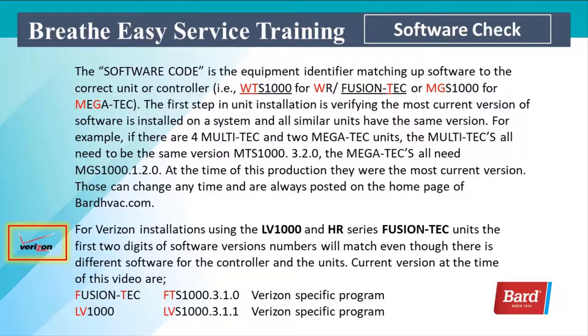The software code is the equipment identifier matching up software to the correct unit or controller. An example would be WTS is for the WR Fusion Tech; MGS 1000 is for the Mega Tech. The first step in unit installation is verifying that the most current version of software is installed on the system, and all similar units have the same version. For example, if there are four Multi-tech and two Mega Tech units, the Multi-techs all need to be the same version of MTS 1000 — that's the unit identifier — at version 3.2.0. The Mega Techs all need MGS 1000 version 1.2.0.